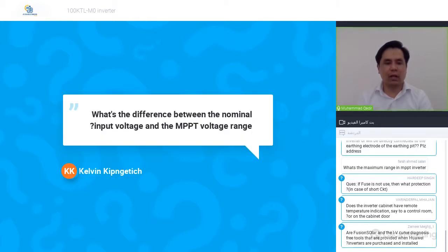Next, what is the difference between the nominal input voltage and the MPPT voltage range? These are kind of the same terminology. It is up to you how you interpret them. But with Huawei inverter, you have two types of MPPT voltage range, which is called nominal input voltage range or MPPT voltage range, and there's another full MPPT voltage range, which is a finer voltage range within which you will get the maximum efficiency of the inverter.